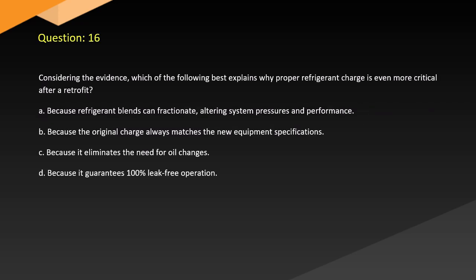Question 16. Considering the evidence, which of the following best explains why proper refrigerant charge is even more critical after a retrofit? A. Because refrigerant blends can fractionate, altering system pressures and performance. B. Because the original charge always matches the new equipment specifications. C. Because it eliminates the need for oil changes. D. Because it guarantees 100% leak-free operation.